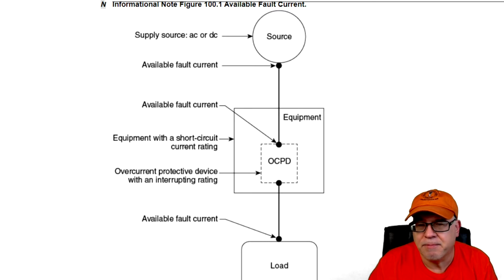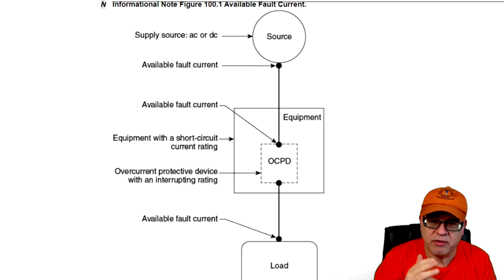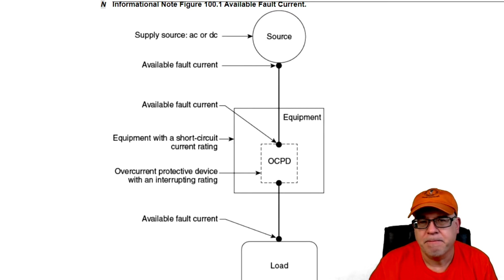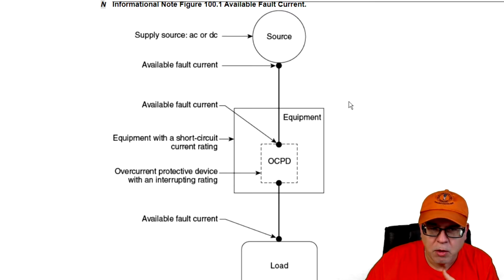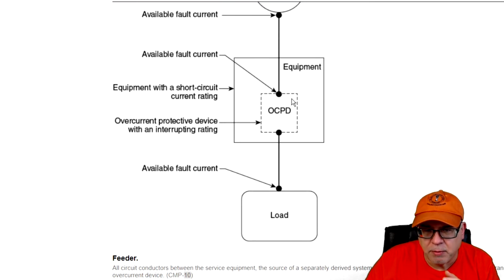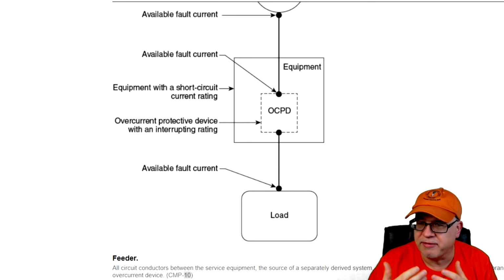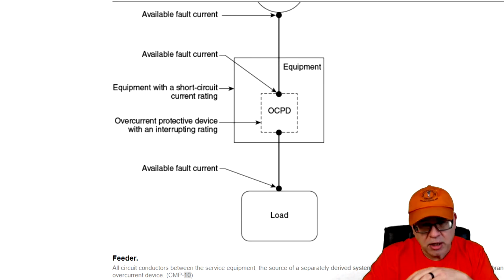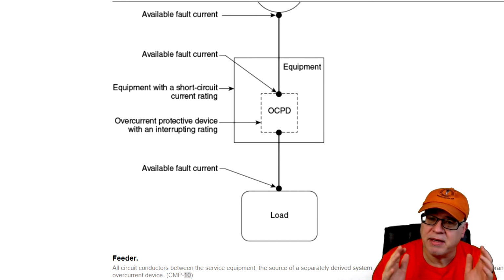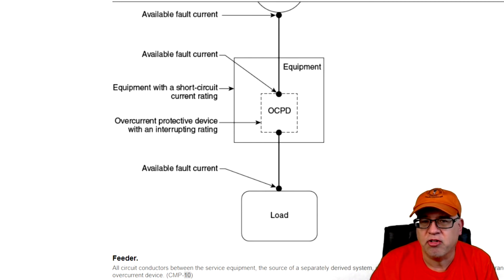Then all you need to do, there's plenty of apps and formulas that you can use. I recommend the app. Cooper Bussmann has a great app for this. It's for your phone. It's a free download. As long as you know the distance of wire, then you can find out what is the available. So in this example, we have an available fault current right here. That's the maximum available fault current at this point on the node. And then you've got wire, which is inherently going to have some resistance in it, obviously. And then you have a point right here, and this is, say, your service equipment, and this is your overcurrent device, okay? And you need to know what the available fault current is right here, because we need to make sure that the overcurrent device has an IR, or an interrupting rating, that is equal to or greater than the available fault current. Now, the equipment itself that the breaker sits in, like the cabinet or the enclosure, also has to have a rating, and that's called a short circuit current rating.